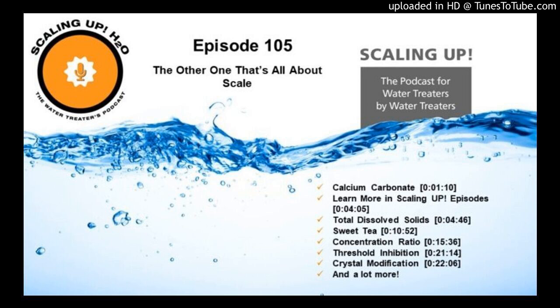This job is not easy, folks. We are heat transfer efficiency managers, meaning that we are dealing with heat, and the water treater's nemesis is calcium carbonate, and the hotter it gets, the more it wants to come out of solution. Now, most things want to go into solution the hotter they get, but calcium carbonate does not do that. It does the inverse effect.